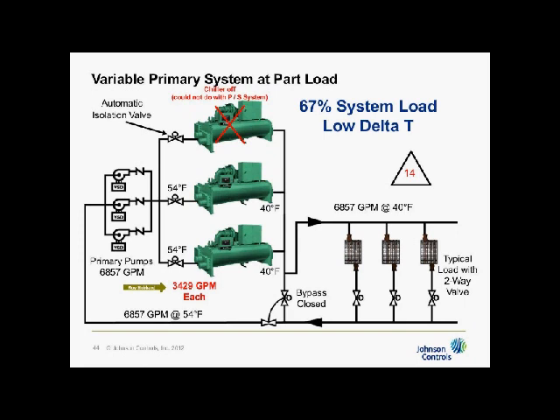Right now I'm at 20 feet at design, so to go to 3429 is a 15% increase in flow, and therefore I'm going to go up to 26 feet instead of 20, which is below the 45. So I can definitely push a lot more flow than what I'm showing here, but it shows you how low delta T can be mitigated in the plant because I can overpump chillers. Going back to our equation, load is equal to flow times delta T. The delta T is down, so I move the flow up. Problem solved at the plant. Now I still have to overpump, so I'm still running these pumps too fast, but I have no choice but to do that until I decide to go out and clean my coils, calibrate my controls, fix leaky valves, etc.